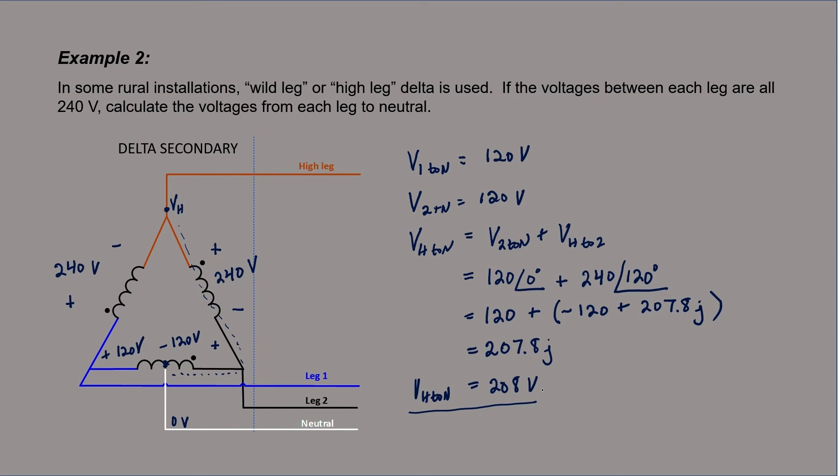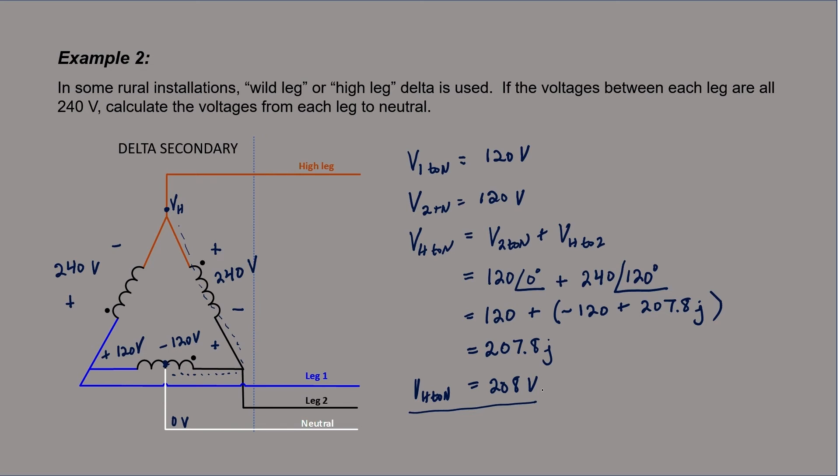The advantage of this kind of wild leg delta in a rural installation is that you can still serve single phase loads because you have 120 volts from either leg one to neutral or leg two to neutral, and furthermore, you can serve three-phase loads at 240 volts between the phases.